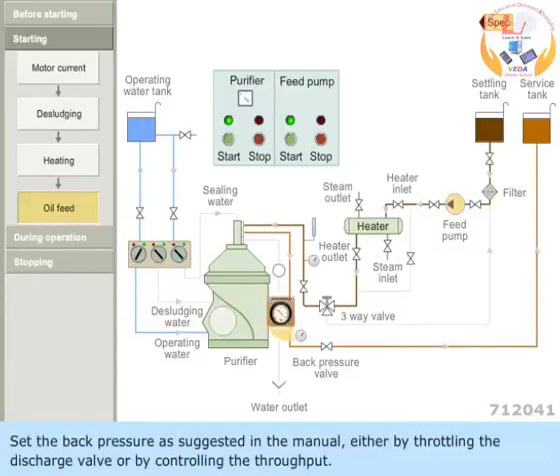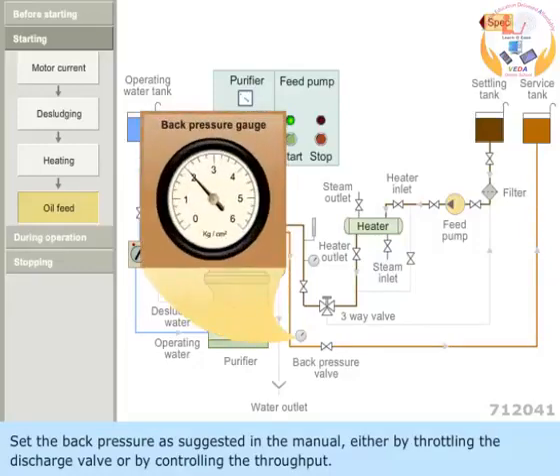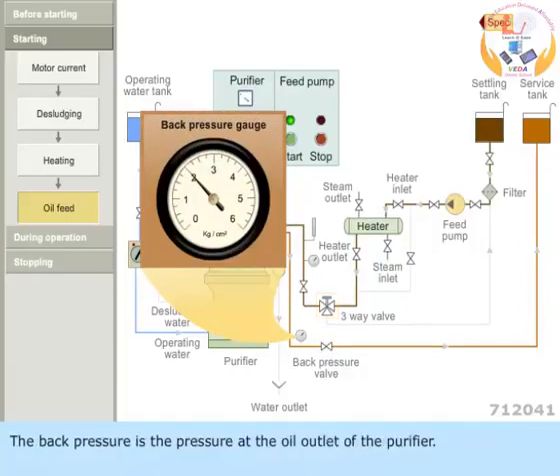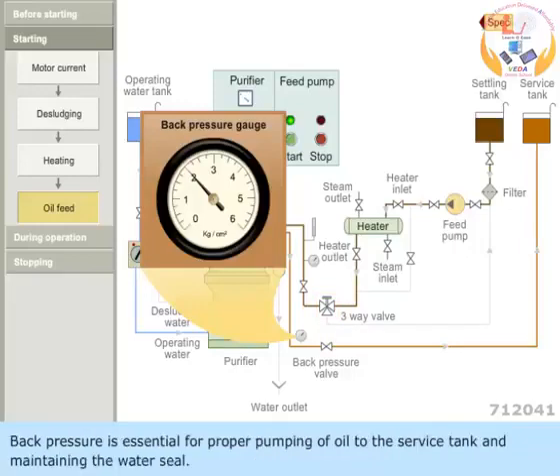Set the back pressure as suggested in the manual either by throttling the discharge valve or by controlling the throughput. The back pressure is the pressure at the oil outlet of the purifier. Back pressure is essential for proper pumping of oil to the service tank and maintaining the water seal.